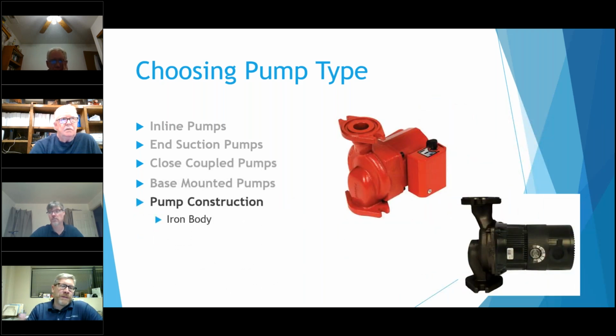After they pick the type of pump they want, the pump construction becomes important. You got listed out here iron body. Those are typically most of the heating and cooling applications. Some of the process applications you can use those on, as long as whatever fluid you're pumping is not attacking the cast iron.